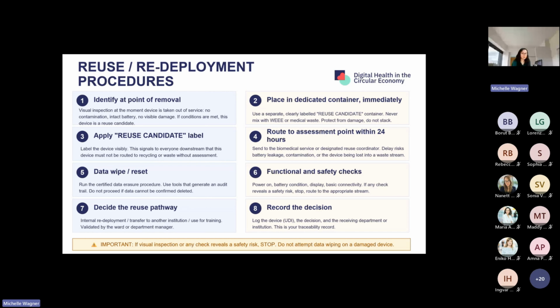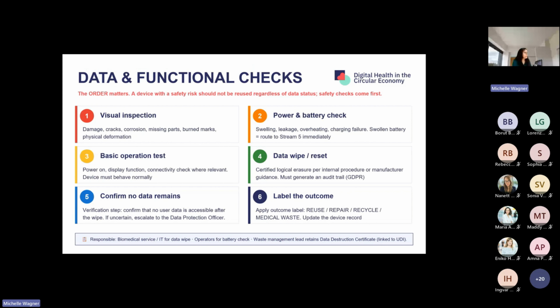And data and functional checks. This is probably one of the most critical stages in the entire reuse process, because it's where patient safety and data protection come together. A device might look perfectly fine on the outside, but appearances, as we mentioned before, are not enough. We need to know if the device functions correctly, what we know about the battery, and we need absolute confidence that no patient information remains accessible.